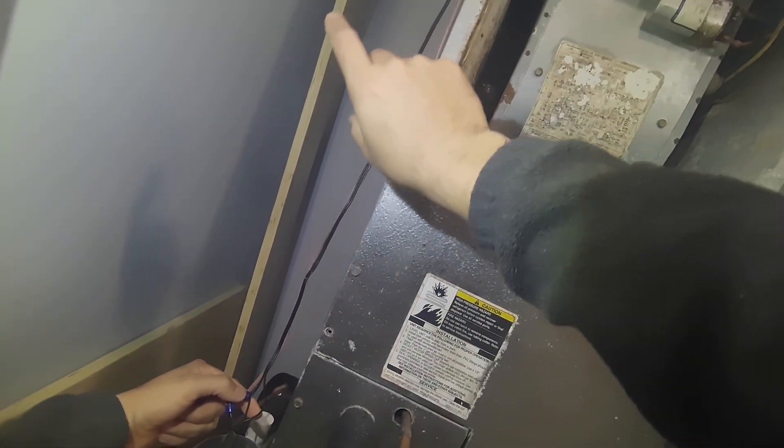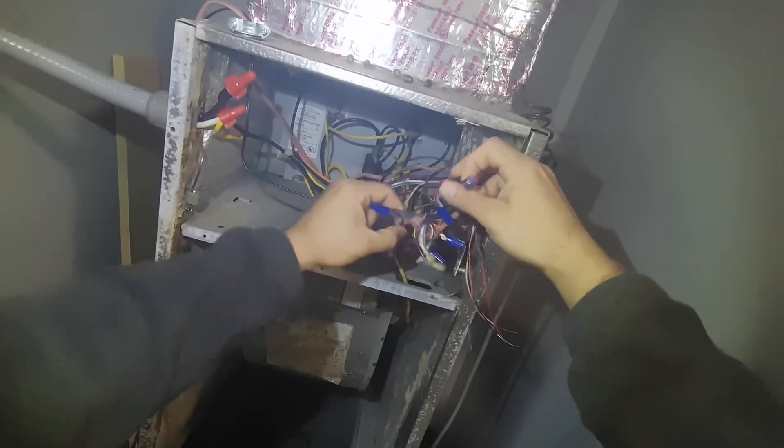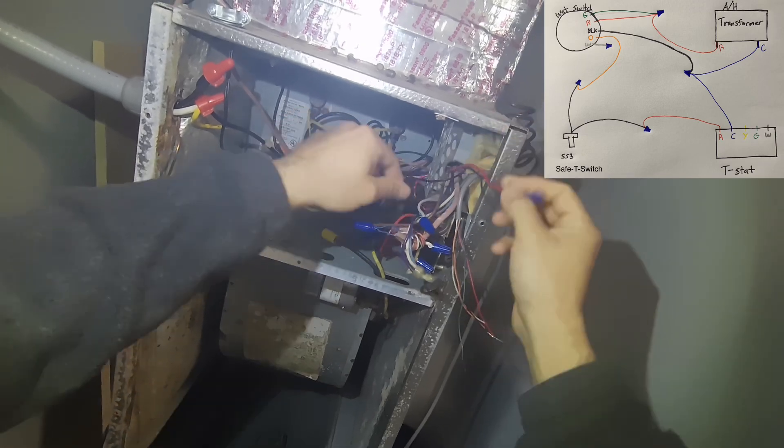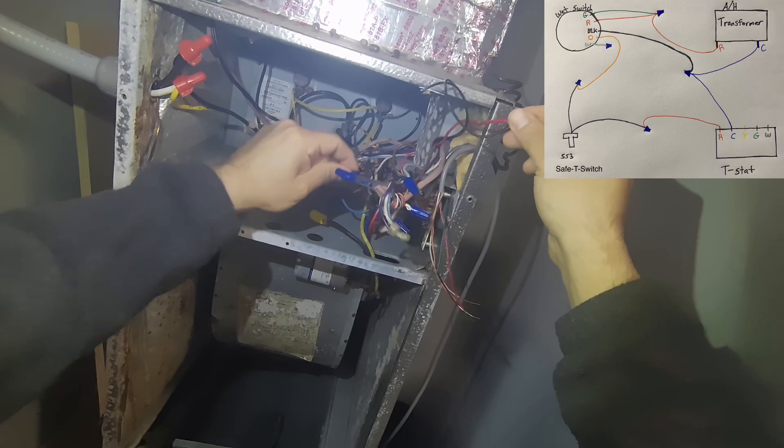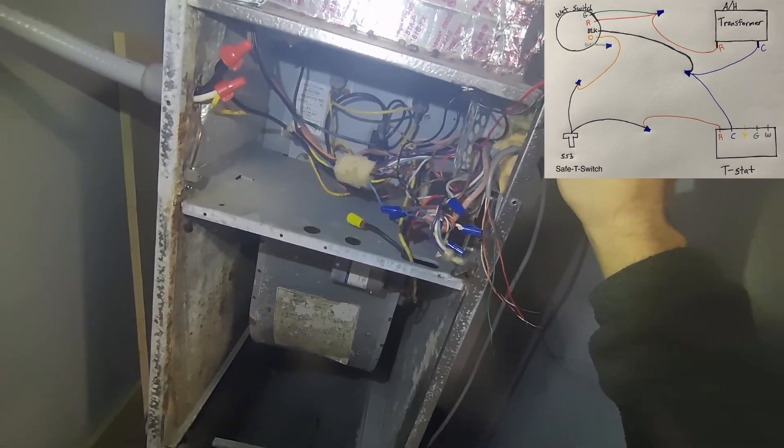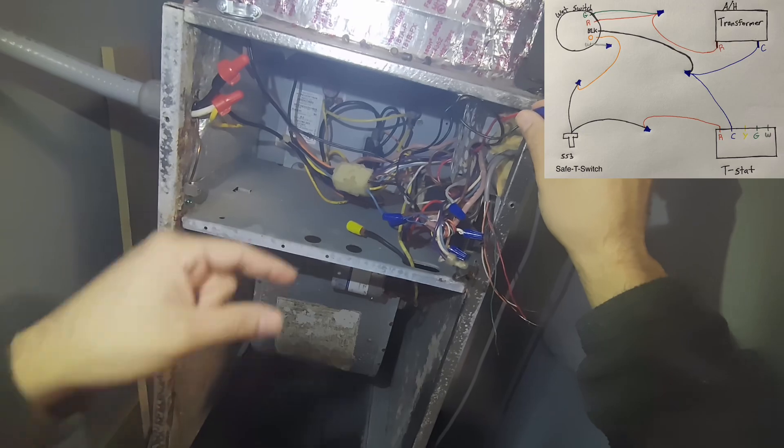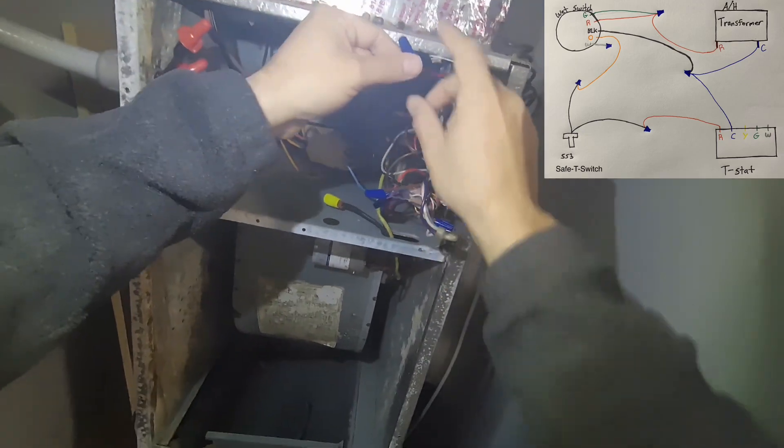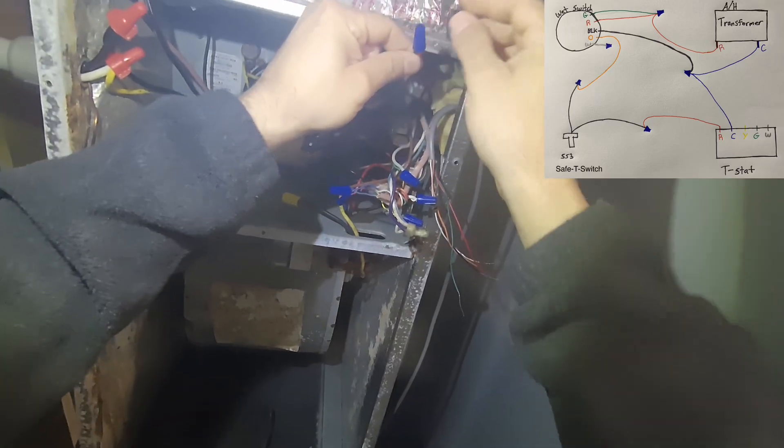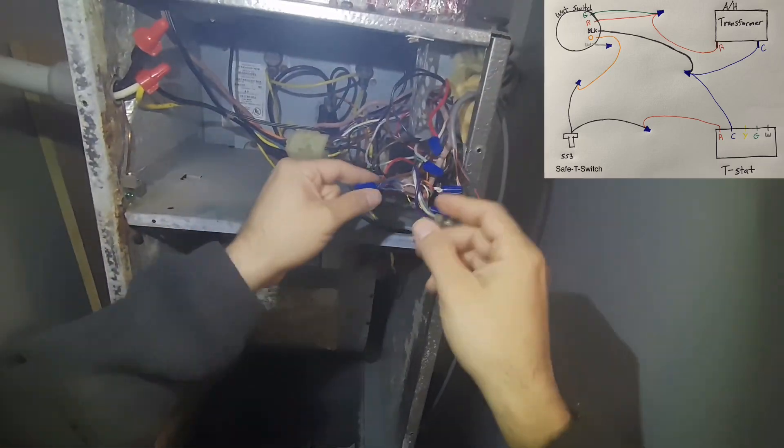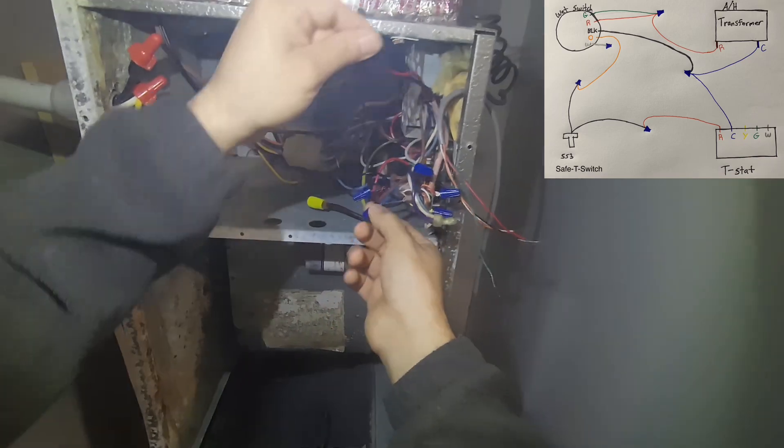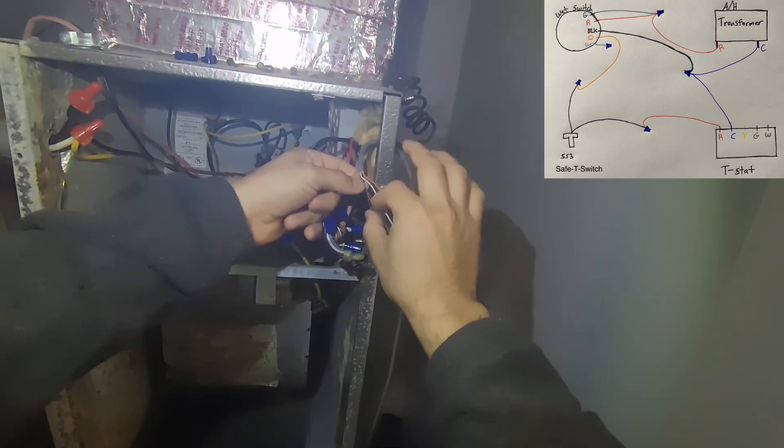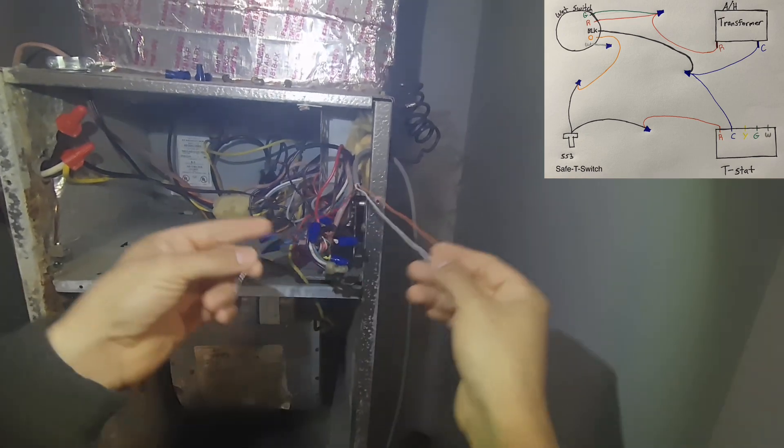Basically we're only going to have one connection for the safety switch, which is this black wire here. If you see this, this is my red wire, this is my power from the transformer, 24 volts. So 24 volts makes it to the board and then from here it connects to your thermostat, so it's a closed loop. We're going to start here with the wet switch.